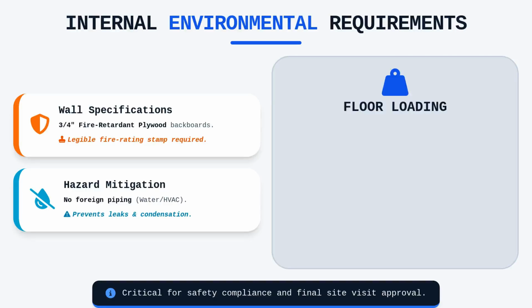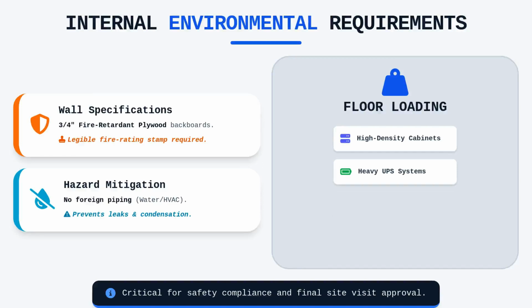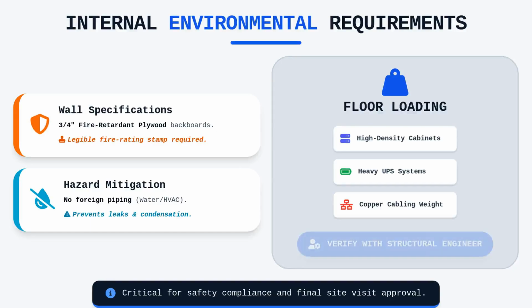Structural floor loading must also be addressed, as floor-mounted cabinets, especially those populated with heavy copper cabling or uninterruptible power supplies, can quickly exceed standard office load specifications. It is your responsibility to verify with the structural engineer that the floor assembly can support the concentrated weight of high-density telecommunications equipment.